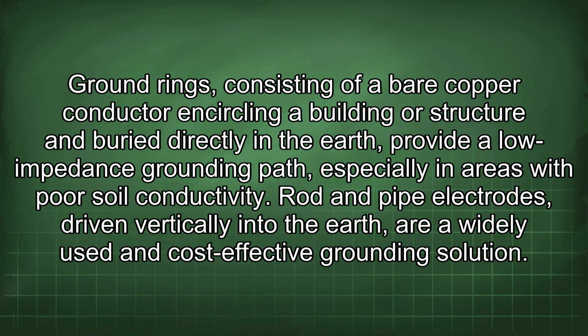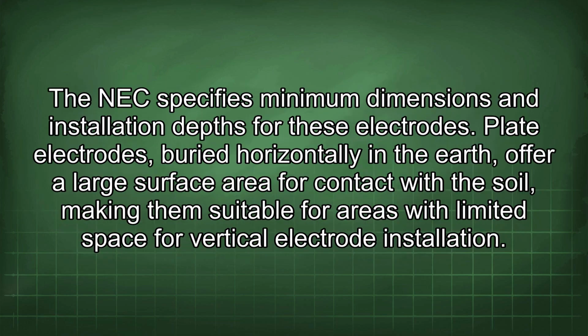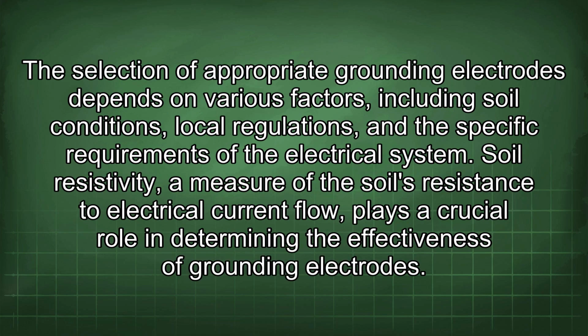Rod and pipe electrodes, driven vertically into the earth, are a widely used and cost-effective grounding solution. The NEC specifies minimum dimensions and installation depths for these electrodes. Plate electrodes, buried horizontally in the earth, offer a large surface area for contact with the soil, making them suitable for areas with limited space for vertical electrode installation. The selection of appropriate grounding electrodes depends on various factors, including soil conditions, local regulations, and the specific requirements of the electrical system. Soil resistivity, a measure of the soil's resistance to electrical current flow, plays a crucial role in determining the effectiveness of grounding electrodes.